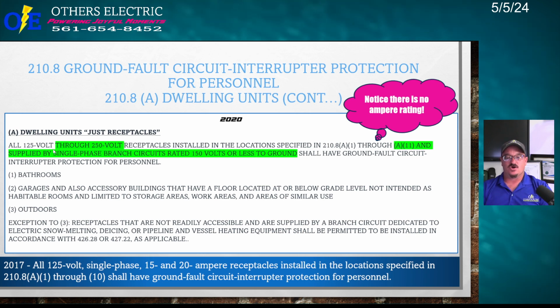Okay, so all receptacles in a dwelling unit in these locations supplied via single phase branch circuit rated 150 volts or less to ground. So what that means is if it's a single phase branch circuit and you put your voltage tester from hot to ground and it's 150 volts or less, this is what is included in this.